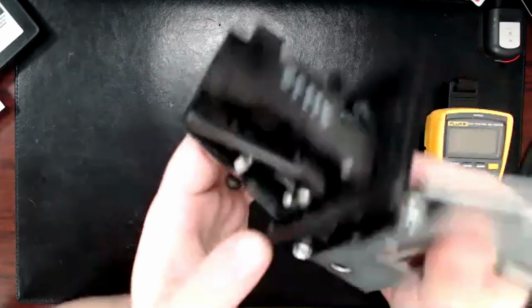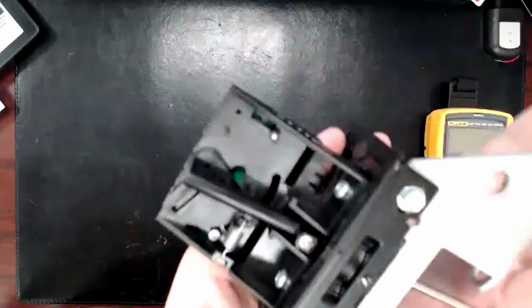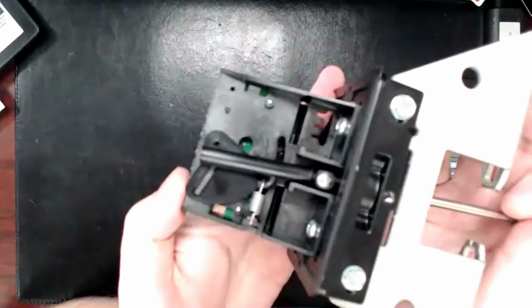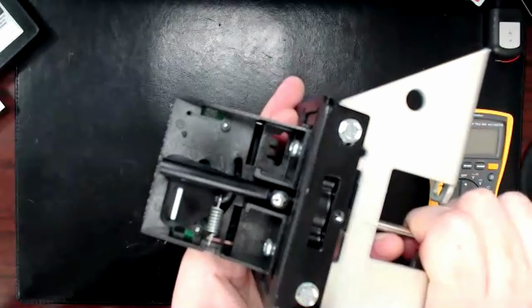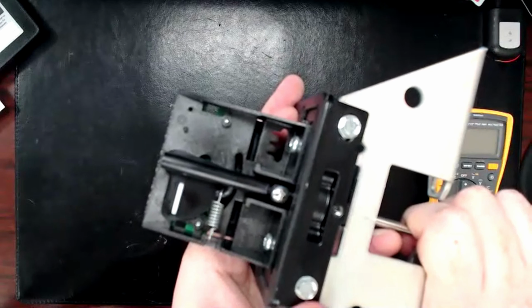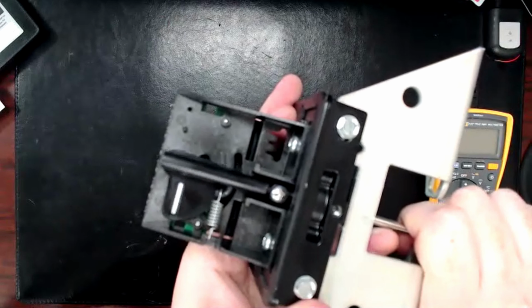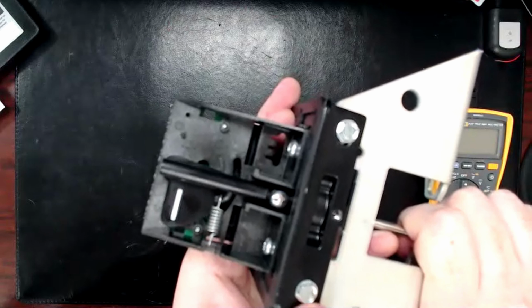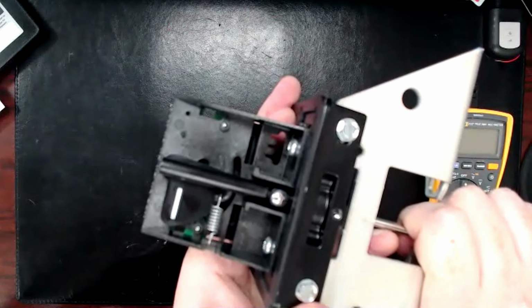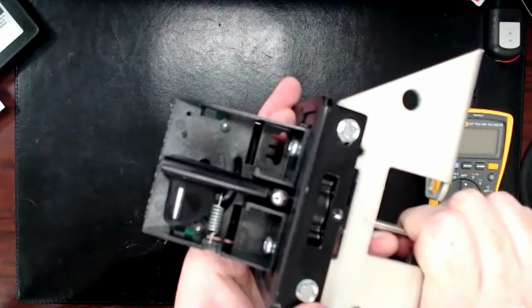And on this particular valve, this is a Potter brand, I believe. You see right here, there's this part, and there's a little window. Whenever it's actually set correctly and that valve is all the way open, there's that little white identifier that you can see through the window. And if you go too far on either side, you see that white doesn't fit quite right. So that's a really quick identifier to know if the valve is set correctly or not.